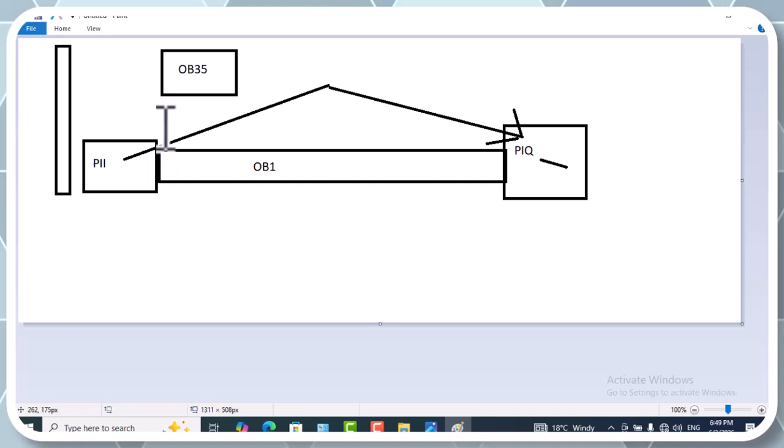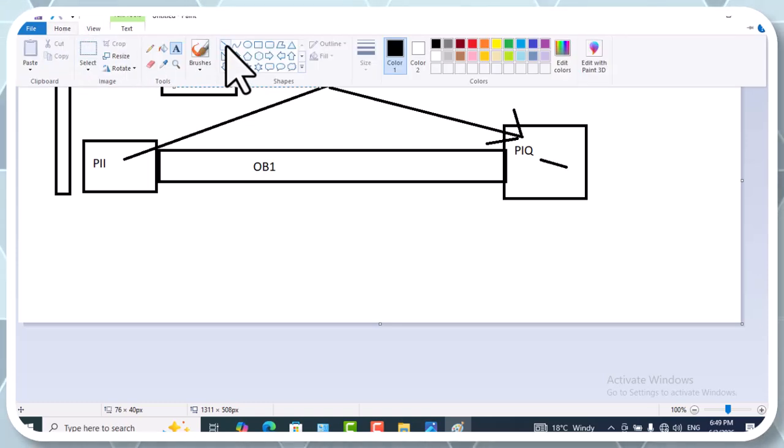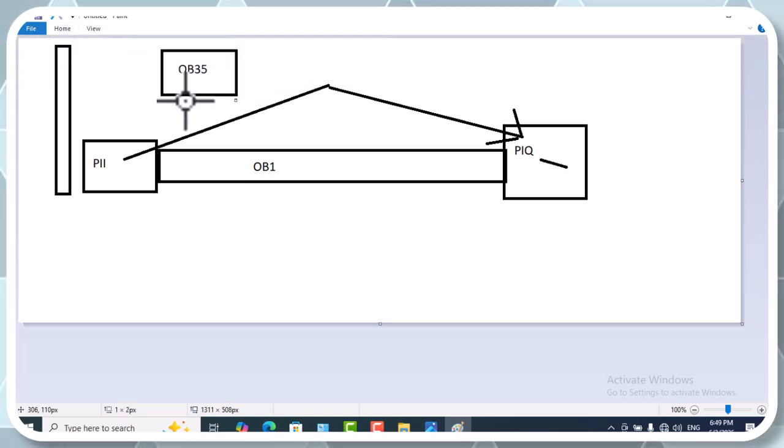This means that when OB1 block is being executed, it stops at the point when the OB35 block is started. It gives all the execution rights to OB35 and waits until this block is finished, and after that OB1 is executed from the point where it stopped, and continues the program.